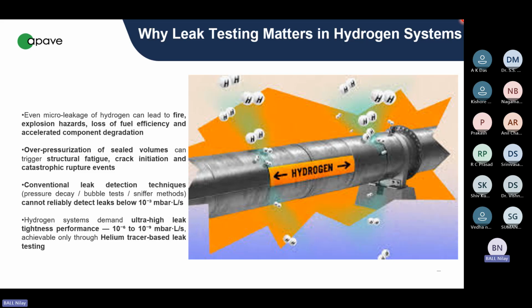In the system, oxygen in hydrogen and hydrogen in oxygen - you rightly said, pure hydrogen doesn't have any problem. If you put a matchstick inside a pure hydrogen cylinder, it will not explode. It's the mixture that causes an issue. So ISO 22734 clearly says 2% of oxygen in hydrogen or 3% of hydrogen in oxygen - either one, the moment it overshoots that, the whole system shuts down.